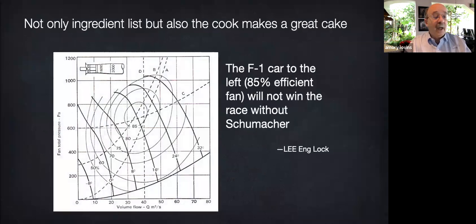Or as Mr. Lee says, in this analogous case of a fan, this fairly efficient 85% vane axial fan is like a Formula One driver. It won't win the race without Schumacher driving it. Errors in its application or installation or operation could easily lose tens of percentage points in practice. Like the US Navy chillers that when we measured them on a ship were among the worst we'd ever seen, even though they'd been superlative in the lab. The difference was that they were installed in the ship with very cramped pipes and ducts set for suboptimal operating conditions, not properly controlled, so they couldn't perform anywhere near the potential that they had correctly exhibited in the lab.